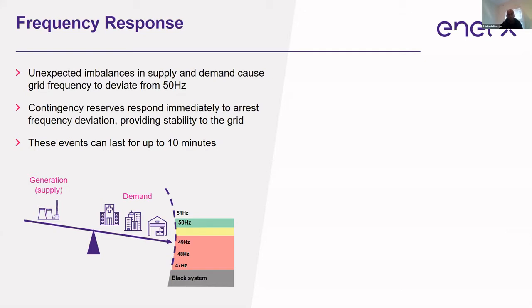It seems quite specific, but the reason that I brought that up is to show you that even the slightest deviation, within 2 decimal places, can cause a significant impact on power quality. So Enel's virtual power plants provide frequency response resources to the grid. In the event of a large power station tripping or a transmission line dropping out, hundreds of megawatts worth of capacity that were once there has suddenly disappeared, and grid frequency will drop off a cliff.